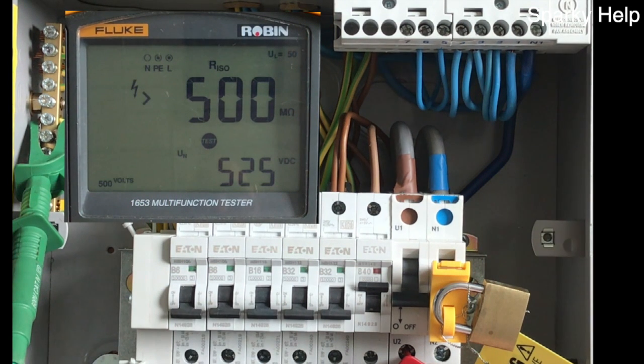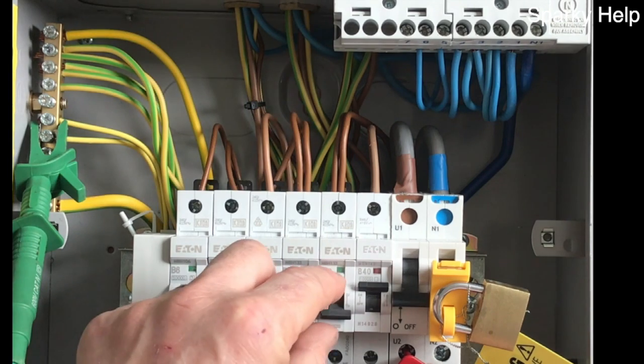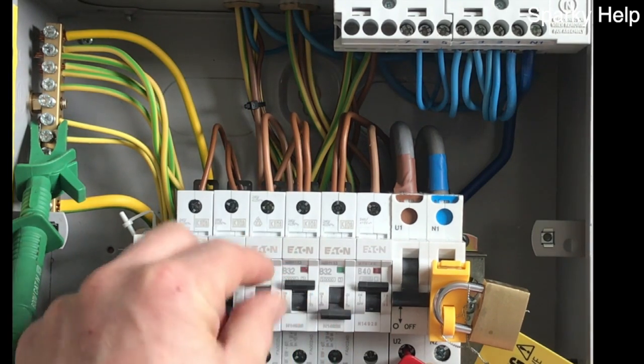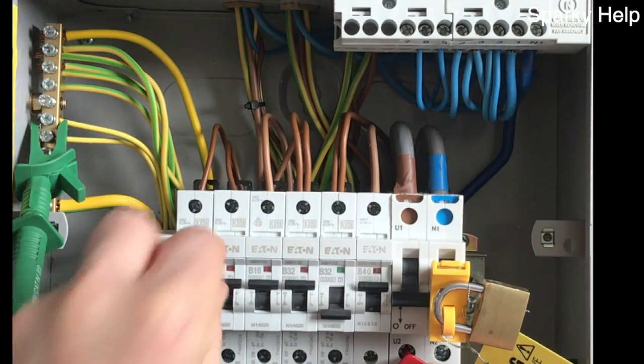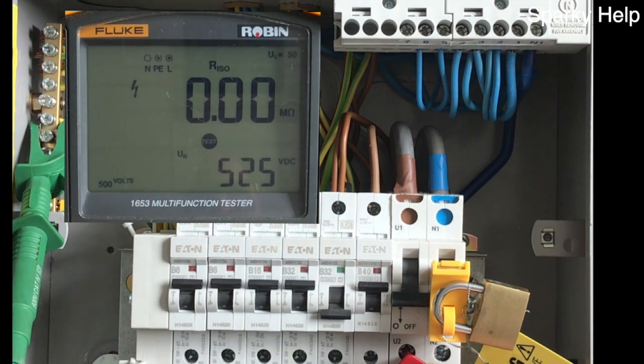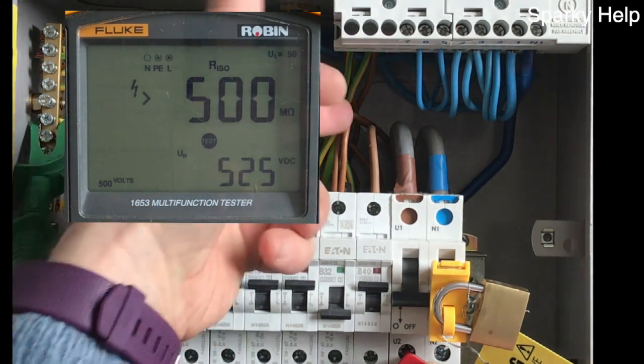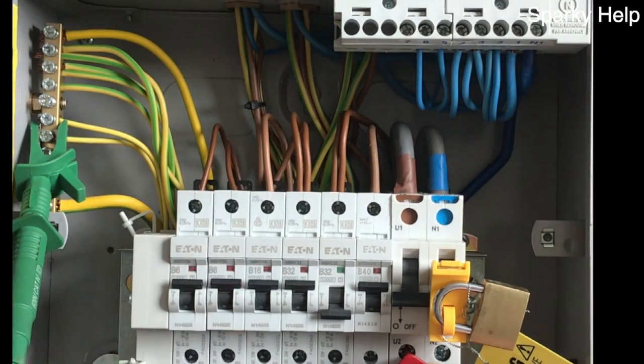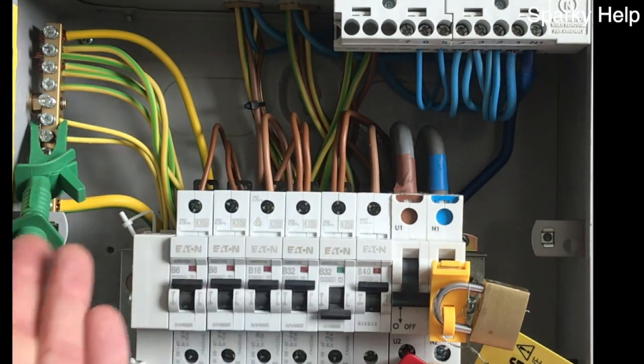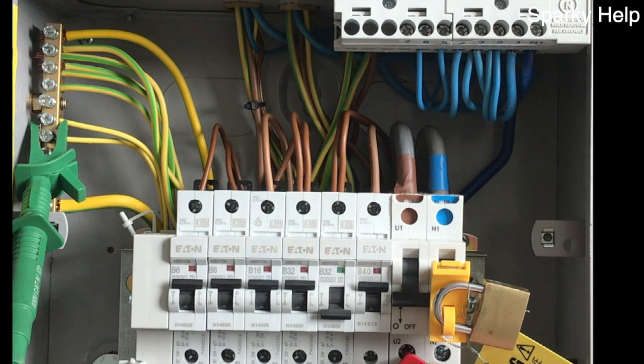Oh, that's clear. So we'll just make sure it is that one. So I'm going to turn all the others back on. So that confirms that it is circuit number 2. And again, this is on a ring final circuit, so we need to break down the circuit between line and earth throughout that installation and find out which part of the circuit is at fault.